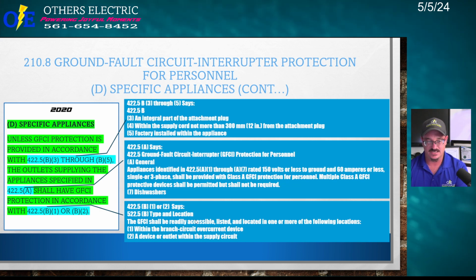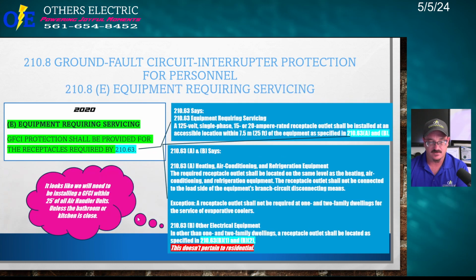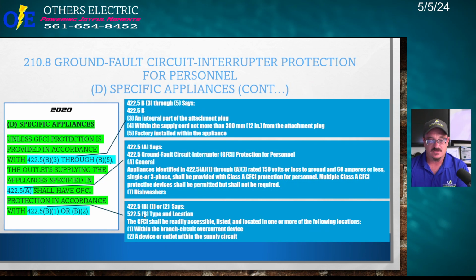All right, and then there's another one that says shall have GFCI protection in accordance with 422.5B1 or B2. So if you go to 420, all right, typo right here. Oh, typo. Okay, 422.5B1 or B2. B1 says GFCI should be in a readily accessible location. It should be listed and located in one or more of the following locations: within the branch circuit overcurrent protection device, the circuit breaker, or a device or outlet within the supply circuit. It's easy. I'm going to stop there because that's all we got.